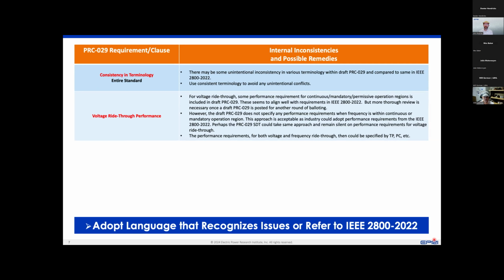For voltage ride-through, some of the performance requirements are included in the draft PRC 29, and these seem to be well aligned with IEEE 2800, but more thorough review is necessary once the next draft is posted. However, the draft PRC does not specify any requirements when frequency is within the continuous or mandatory operation region. This approach is acceptable from our review because it would allow the transmission planner to then specify, for example, frequency response during normal operation.